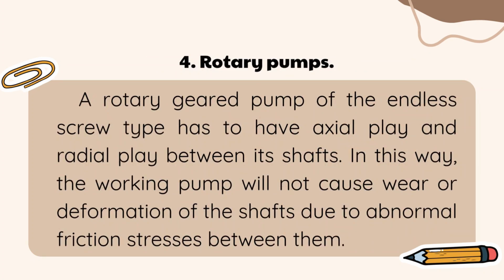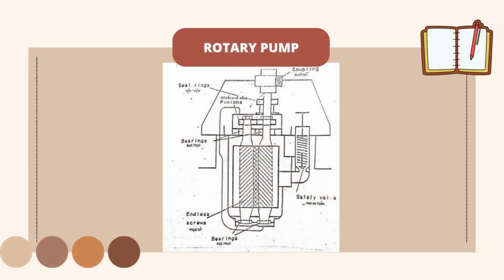4. Rotary pumps. A rotary geared pump of the endless screw type has to have axial play and radial play between its shafts. In this way, the working pump will not cause wear or deformation of the shafts due to abnormal friction stresses between them. Rotary pump.